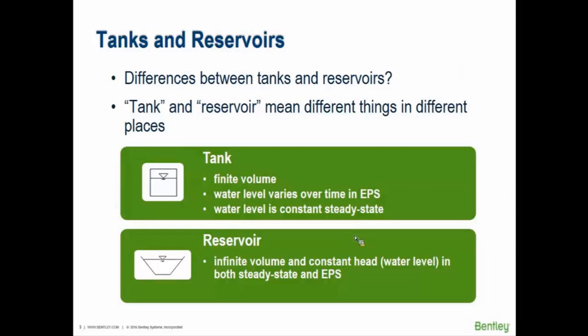In the first few workshops you dealt with a tank. During a steady state model the tank could be an infinite diameter — what really matters is the water surface elevation, the potential energy, the head elevation in that tank when looking at pressure. When running extended period simulation, storage becomes critical for knowing how quickly the tank is drawing and filling. Steady state is just a snapshot based on boundary conditions — the tank water level, not tank diameter.